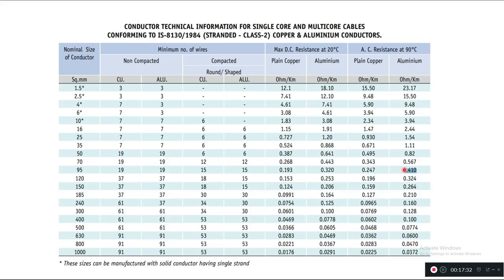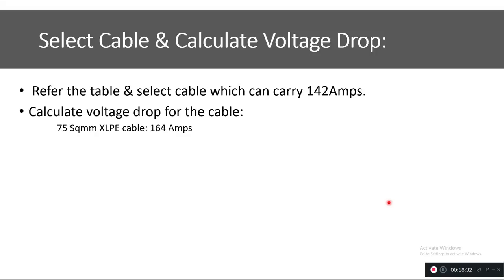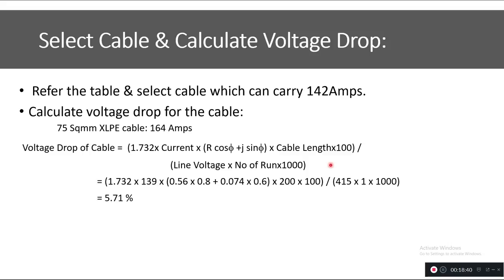From the cable datasheet, the resistance for the aluminum AC cable is 0.567 Ω/km for 70 mm² and 0.4 Ω/km for 95 mm². We also need the reactance values for both sizes. I recommend checking both 70 mm² and 95 mm² because if the 70 mm² does not satisfy the voltage drop condition, we will move to 95 mm².